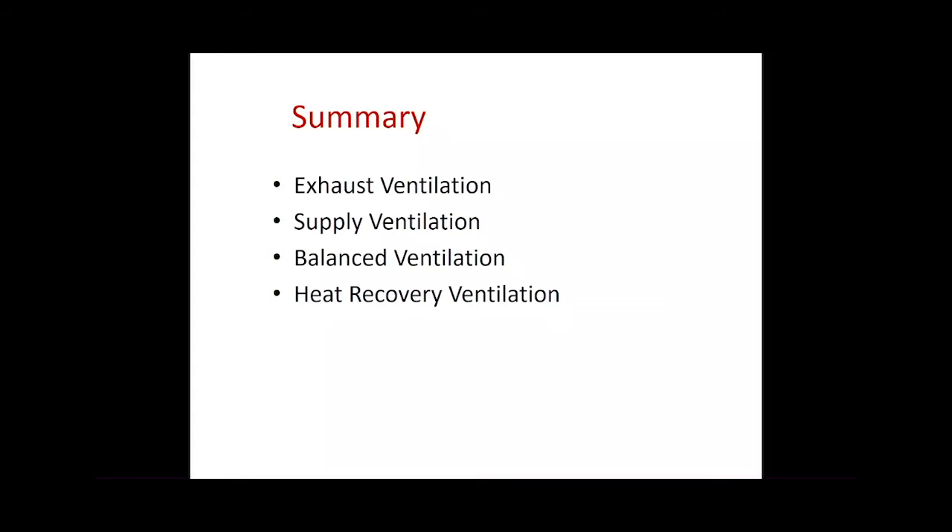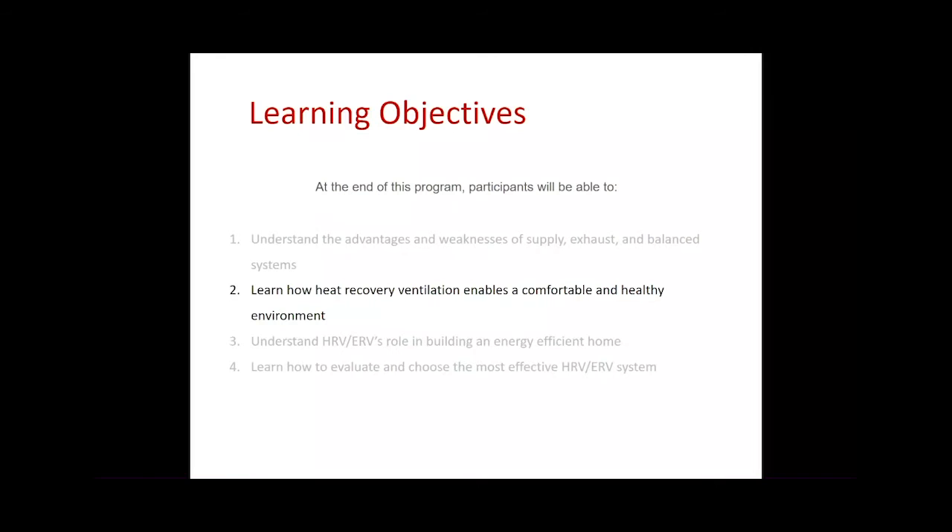Please try to do balanced ventilation — you don't need passive house levels of air tightness to benefit. If your house has 20 air changes per hour at the blower door test — very bad but not uncommon in older buildings — focus on envelope improvements first. But most houses would benefit from a balanced ventilation system, both for filtration control and energy savings. Heat recovery ventilation is critical even in hot climates, because it reduces incoming air temperature and lowers cooling requirements.